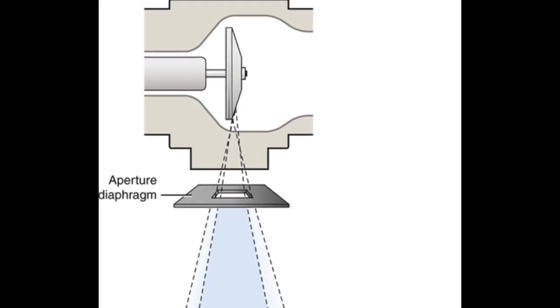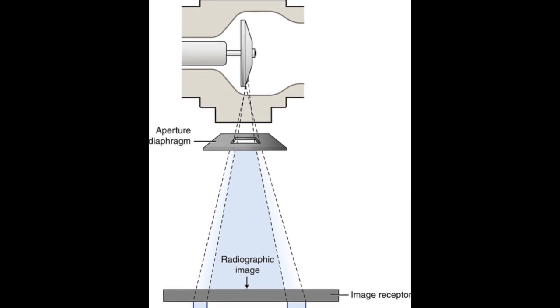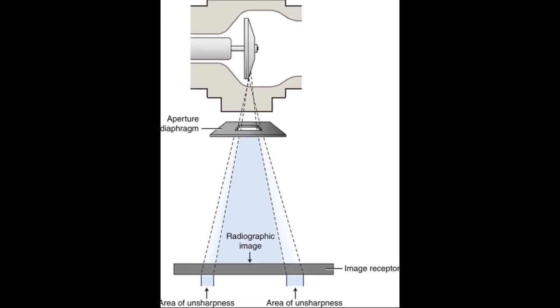Integrity of beam alignment and collimation are extremely important, both in avoiding the practice of unnecessary radiation of tissues not being imaged and to reduce the likelihood of cutoff resulting in repeat imaging and therefore increasing exposure. There are multiple areas where discrepancy can exist that can lead to unexpected image results. They can occur with the collimator, or where the light field is not consistent or poorly calibrated with the beam, with the alignment of central ray and or with the alignment of the bucky, or with specified distance indicators resulting in inaccurate measurements of desired exposure as a function of distance.